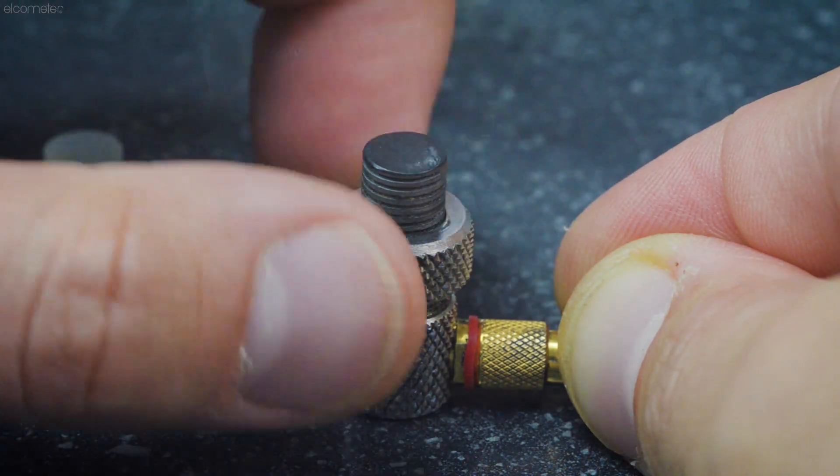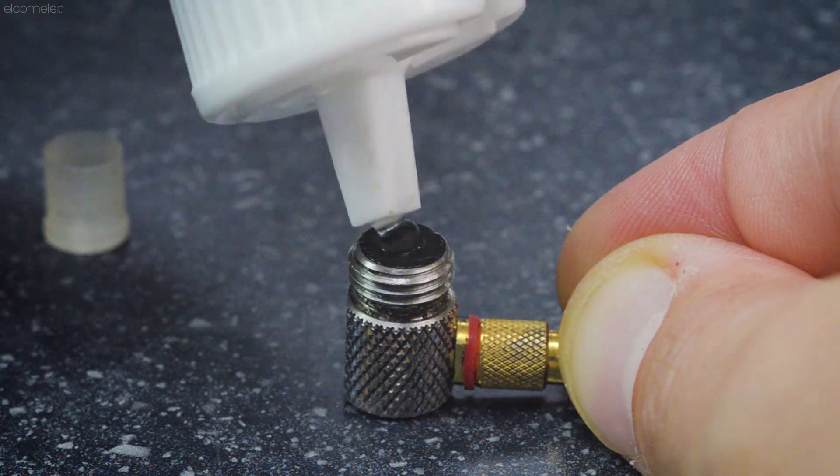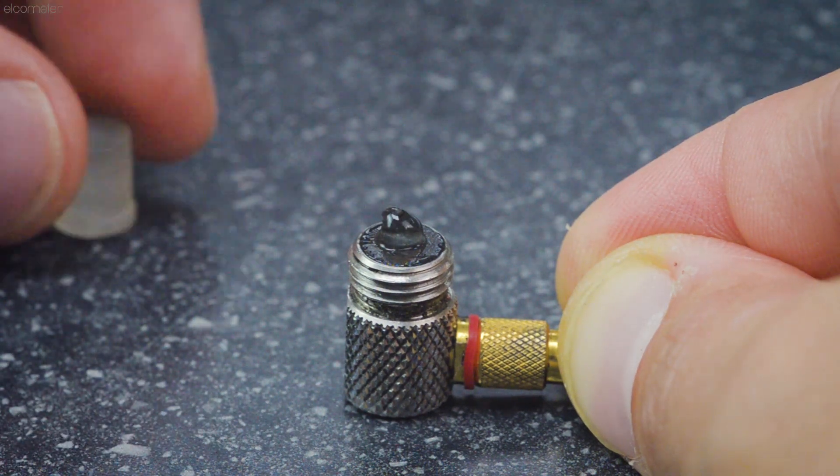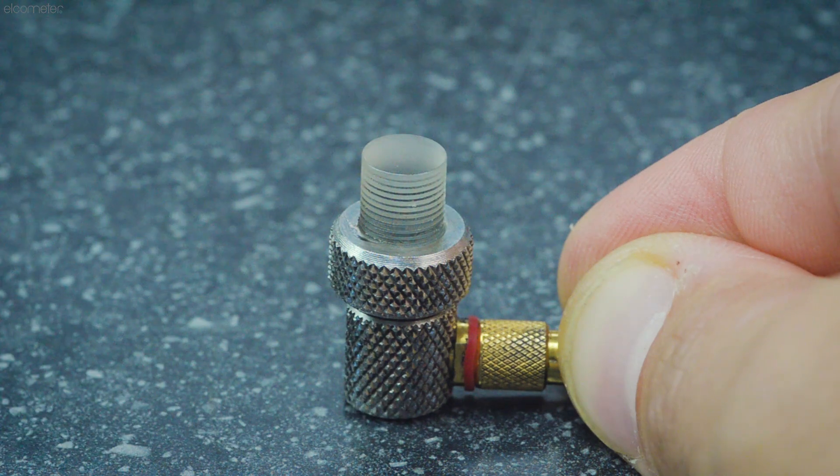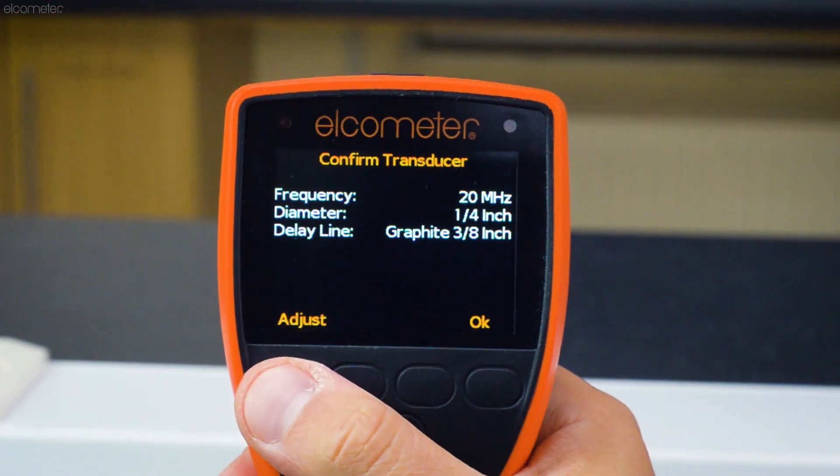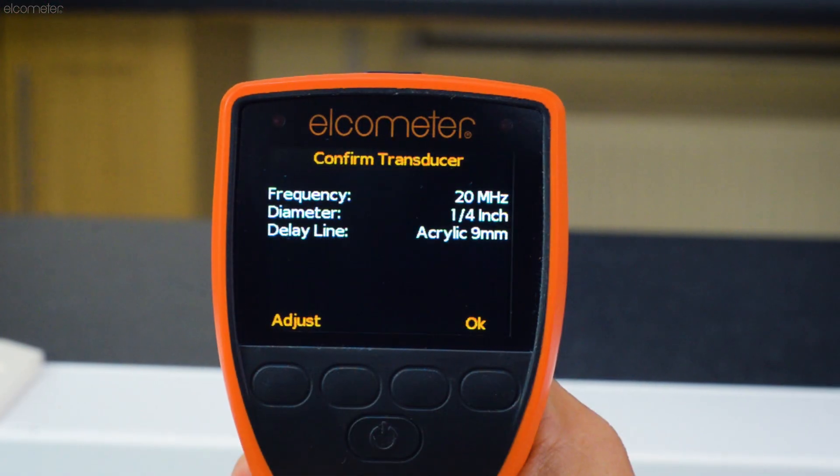Whenever you change delay lines, you should ensure there's a small amount of ultrasonic coupling between the delay line and the transducer, making sure there's no free air between them. And always remember to change the delay line setting within the gauge.